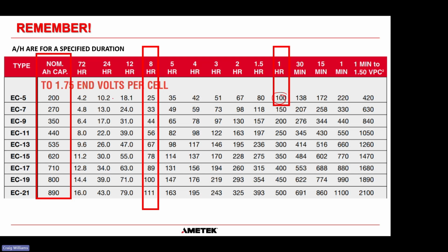And in truth, if you go past the 8-hour rate and you go to the 24-hour rate, if you multiply 10.2 amps by 24, the capacity will go up. That actually adds up to, I think it's 248 ampere hours.